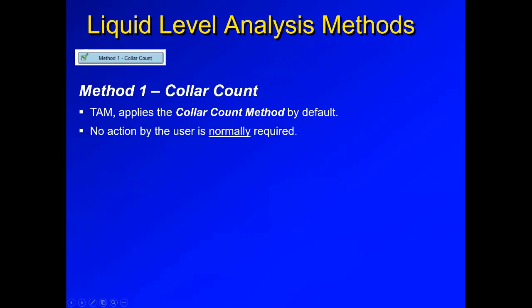Most of the time, when there are collars to count, no action is required by the user. It's kind of alarming, but we get phone calls from people who've been shooting fluid levels for a while saying they've never done anything - they just connect the equipment, shoot the fluid level, and print the report. The good news is the software most of the time does the work for you: it picks the liquid level, counts the collars, and gives you a very good distance to liquid level calculation automatically, without user intervention. On some wells you may have to intervene, where the liquid level isn't picked properly or the collar count is poor, and you may need to shoot with more pressure. We'll talk about those topics as well.